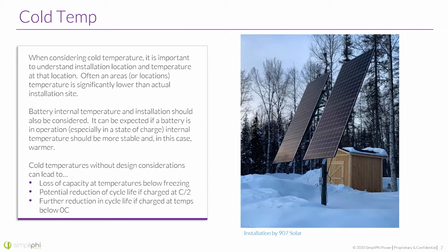Cold temperatures without design considerations can lead to damage. What can happen when charging in cold temperatures, or when discharging below the cold temperatures that we recommend? You can see a loss of capacity at temperatures below freezing, and a potential reduction of cycle life if charged at C/2. Again, the SimpliPhi has this intelligence built in where it can ramp down charging even below that 0, to allow a little bit of leeway. With charging, the lower the charge rate and the lower the temperature, the less damage you can likely do. But if you're charging at, let's say, C/2 and you're way below the temperature restrictions, you could definitely and probably will hurt the battery. There's a further reduction in cycle life if charged at temperatures below 0 C. So this is really the unfortunate thing that's going to happen if the guidelines aren't met.